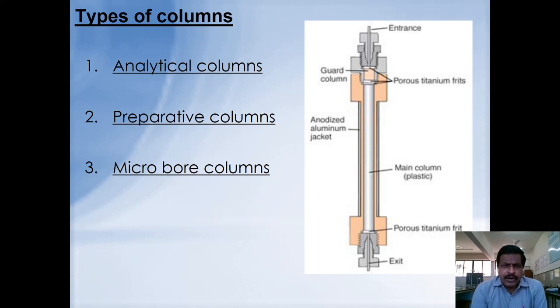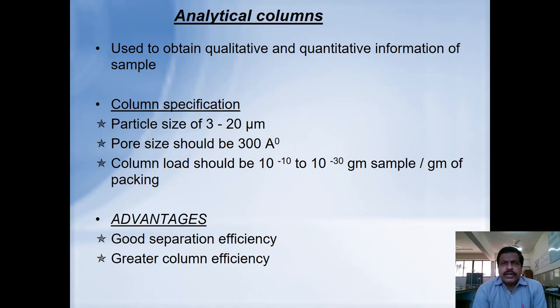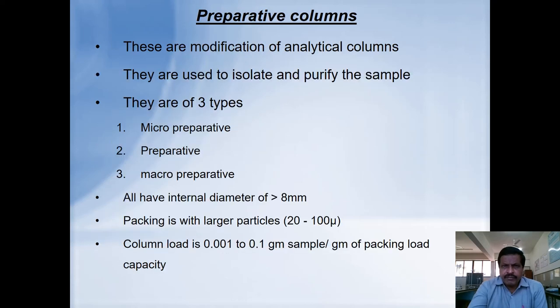There are different types of columns: analytical column, preparative column, and microbore column. The analytical column is used to obtain qualitative and quantitative information about the sample. Particle size ranges from 3 to 20 micrometers and pore size should be 300 Å. Column load is 10⁻⁴ to 10⁻³ grams of sample per gram of packing. The analytical column gives good separation efficacy. Preparative columns are modifications of analytical columns used to isolate and purify samples, with sub-types including micro-preparative, preparative, and macro-preparative.